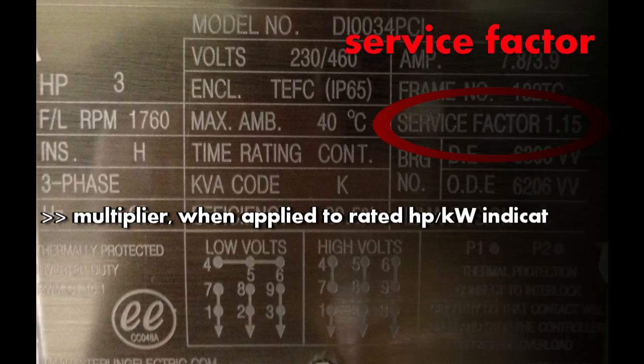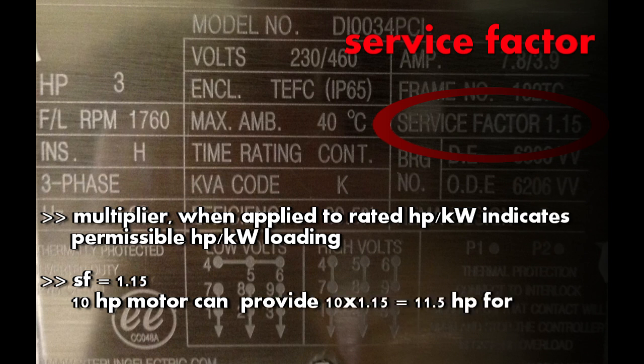Next is the service factor. It is a multiplier which when applied to the rated horsepower gives you a permissible horsepower loading which you can carry out for short duration at rated voltage and frequency. Suppose you have a service factor of 1.15. That means a 10 HP motor can provide 11.5 HP for short term. Operation at service factor load for extended periods will usually reduce the motor speed, life and efficiency.